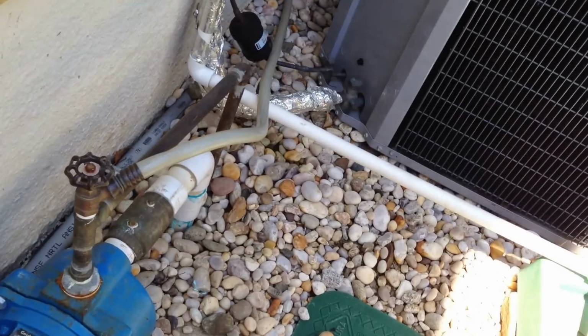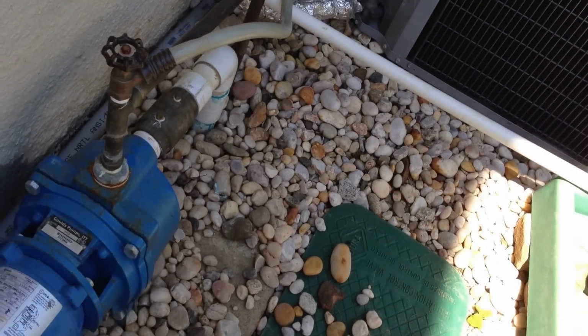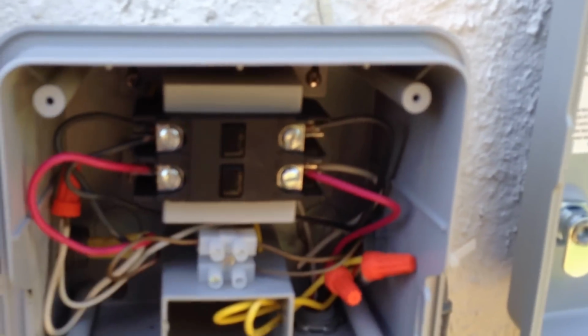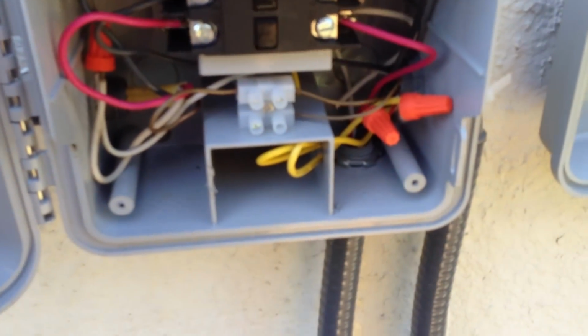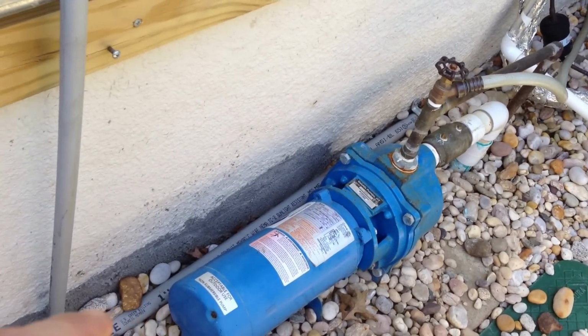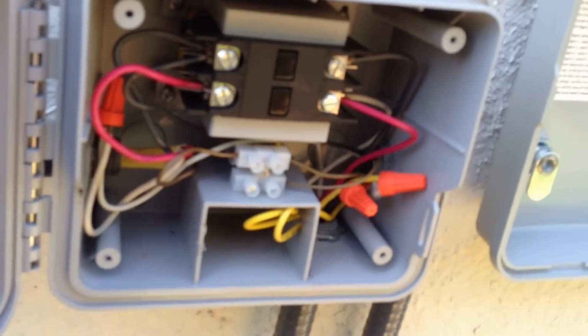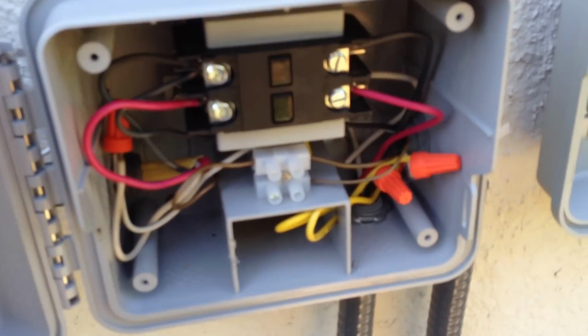When it wants to turn on, it sends 24 volts to the electrical switch that turns on that zone, and then it sends 24 volts to this relay. Here is a relay box, and what this does is send 240 volts down to the pump. A relay is just a switch. You can use a thin 24-volt wire into this box, and then it'll send 240 volts into the pump, so you don't have to run the 240-volt wires back and forth. You can look up relays on the internet. So we'll give this a start, and we'll see how much electricity it's using.